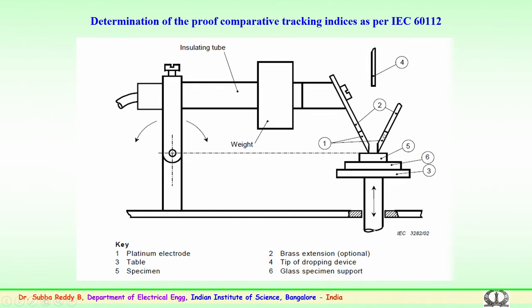Here you have 2 electrodes, where the electrodes are of platinum edges with a brass electrode arrangement. Then you have the weight to apply the proper mechanical force which is kept on the sample. This is the sample, the specimen, the silicon rubber or the sample which is to be under test, and below that is a glass specimen support for the sample, and this is a small stand.